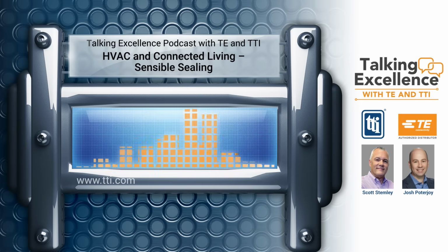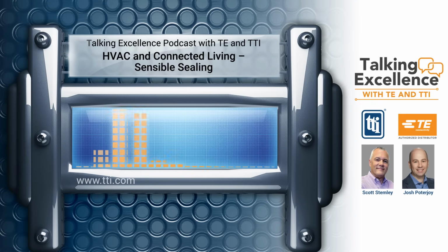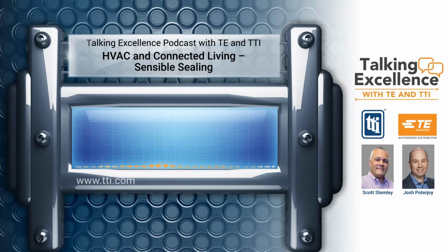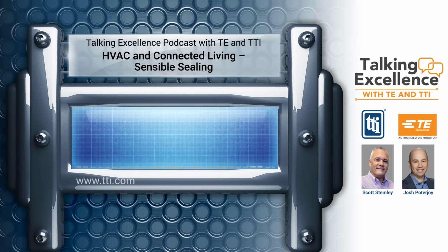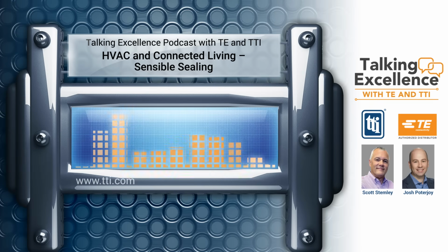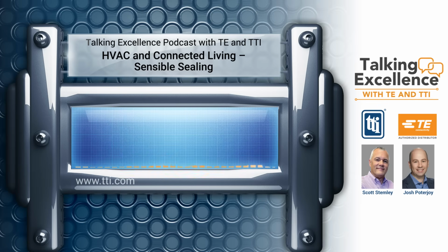And really, just a little bit of background on that product rating. You'll see an IP for ingress protection and then two numbers following that. Those two numbers really tell you the level of protection that product has. So the first numeral is the solid ingress protection, and that goes from 0 to 6, 0 being the least protection, 6 is dust tight. So as you go up that scale, as you can imagine, you get more and more protection.